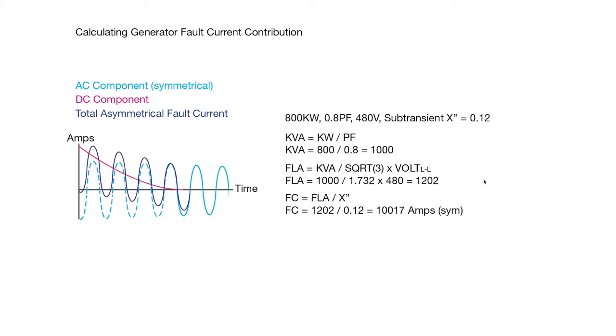And next we take that FLA and divide it by the sub-transient reactance, and we get a fault current of 10,017 symmetrical amps.